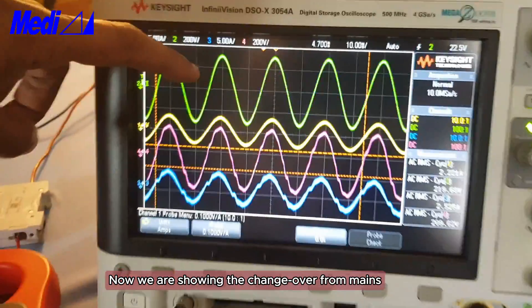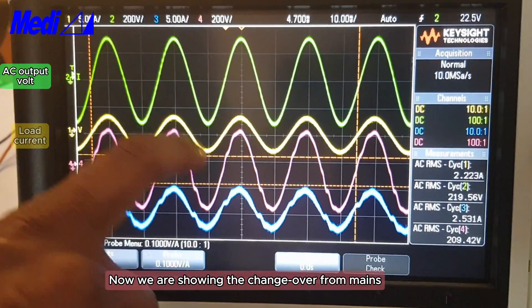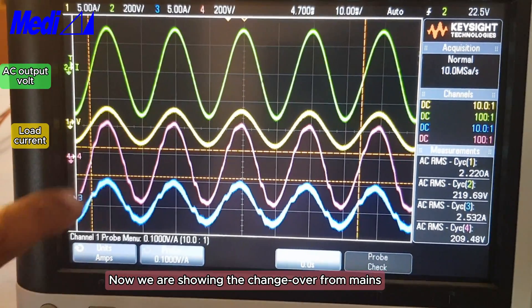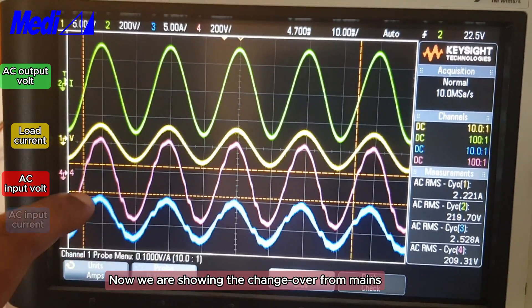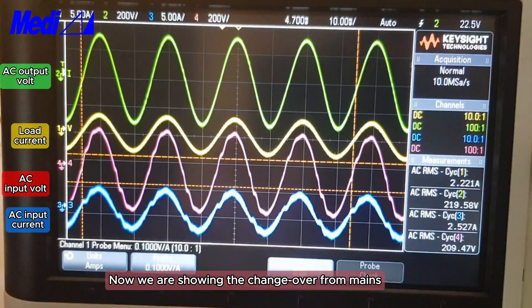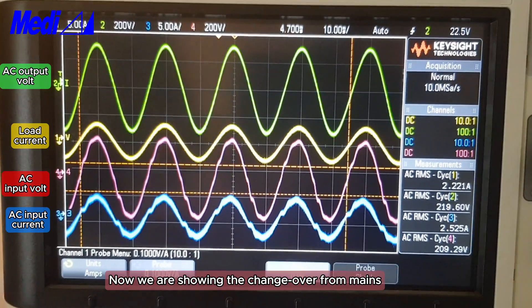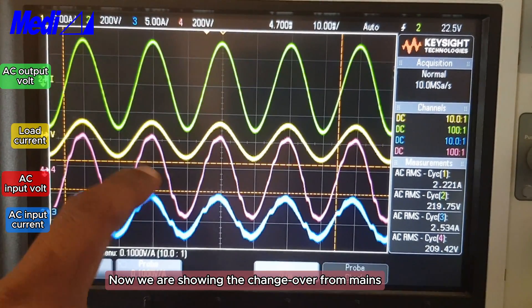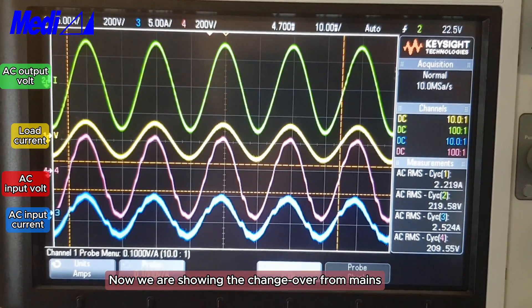You are seeing: green is AC output voltage, yellow is the load current, blue is the mains input current. Now I will switch off the mains AC — you can see the UPS output remains the same.